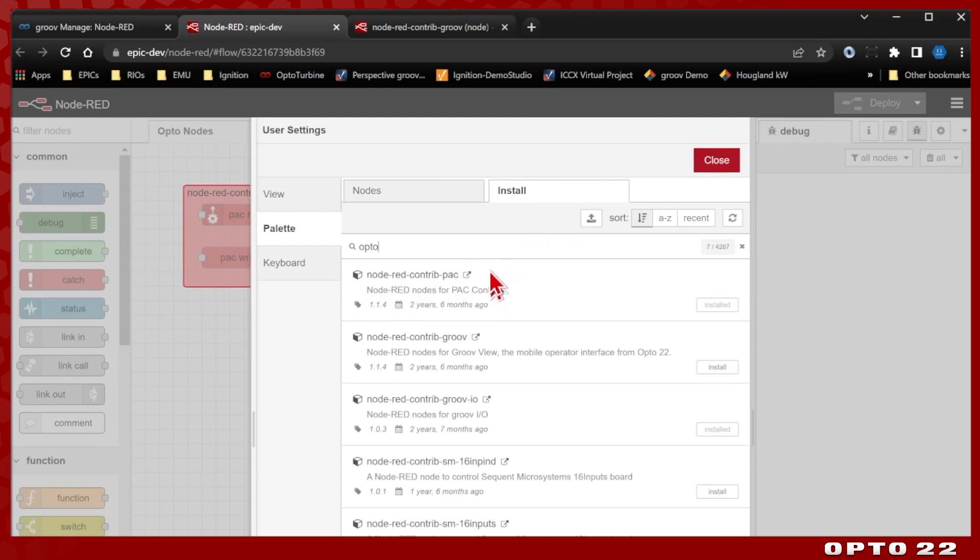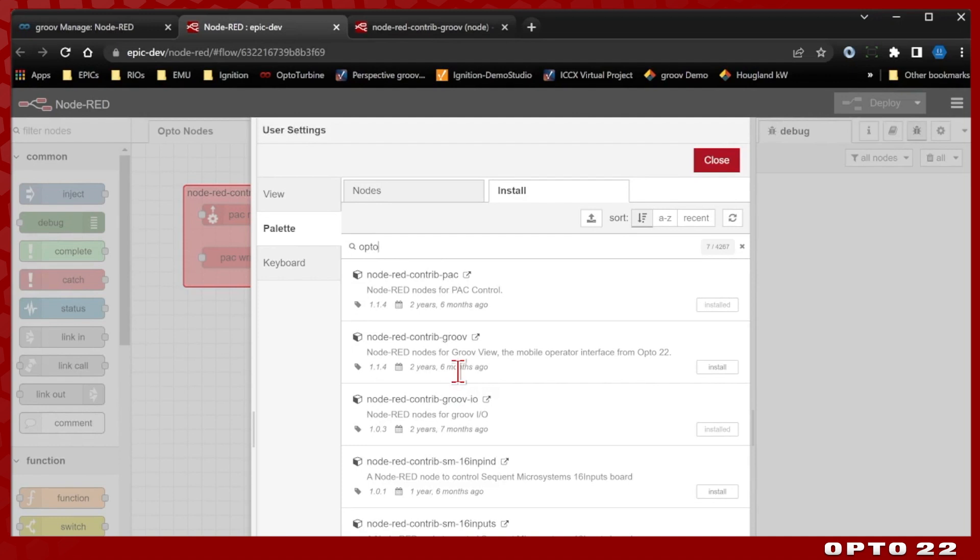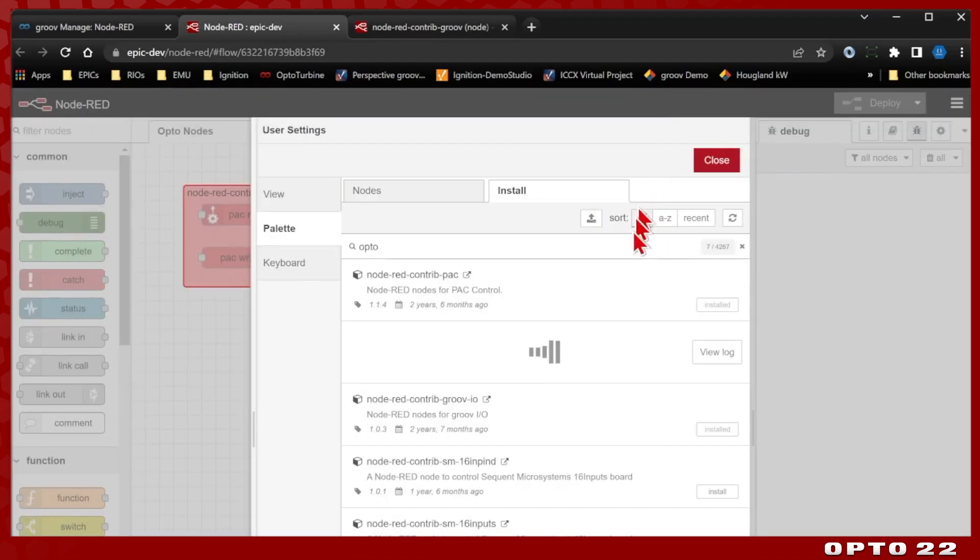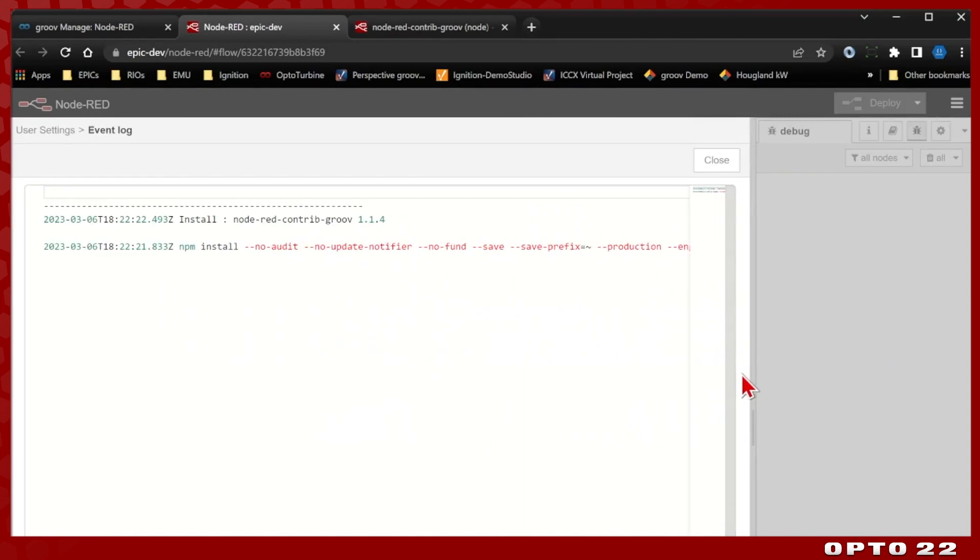And you can see here we have the PAC and groov IO nodes and we need to install this contrib groov. You'll note that the groov IO nodes are used for the modules that are attached and you'll reference them by their module number and the index of the channel you're using, whereas the groov nodes are used for the groov View HMI. So we'll install those now, select install and you can view the log to make sure everything comes down properly.